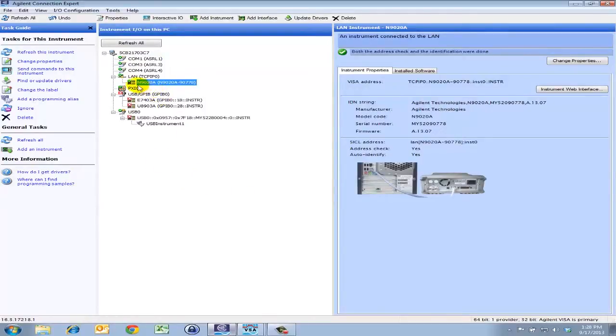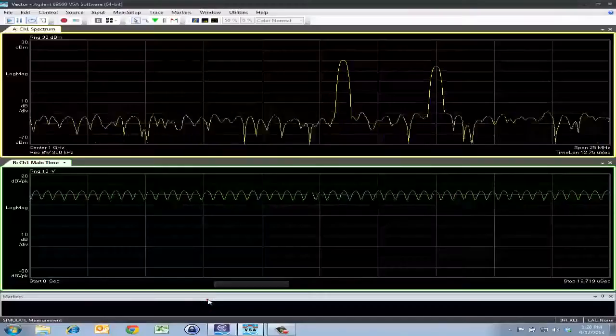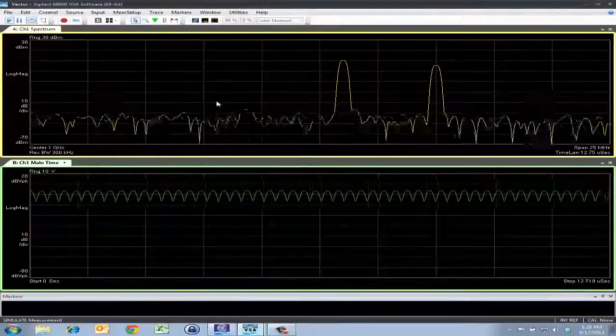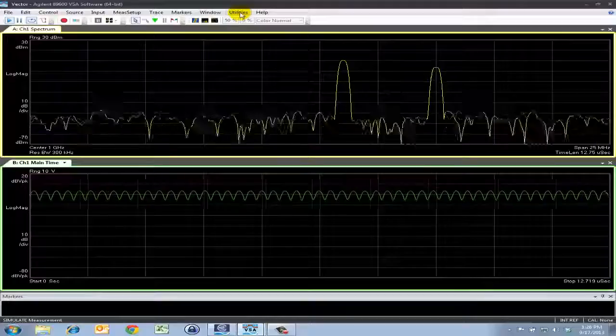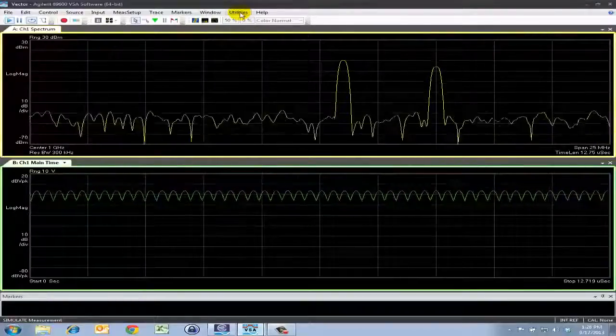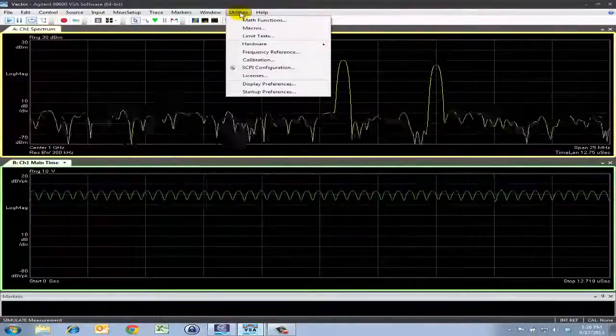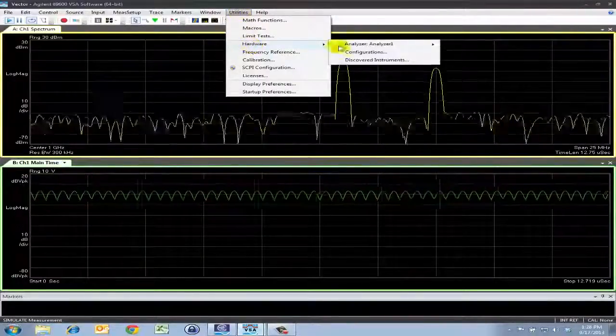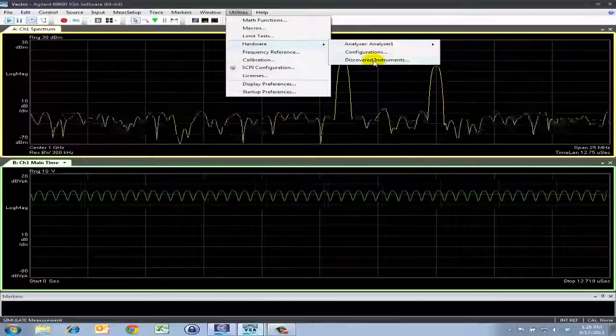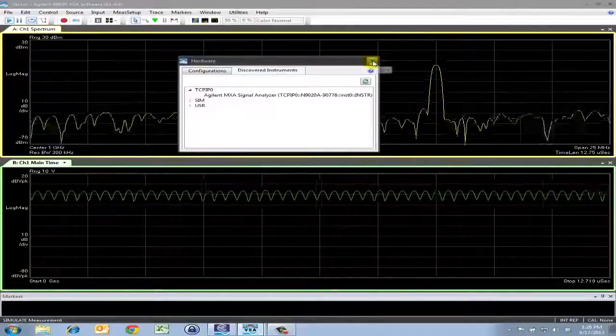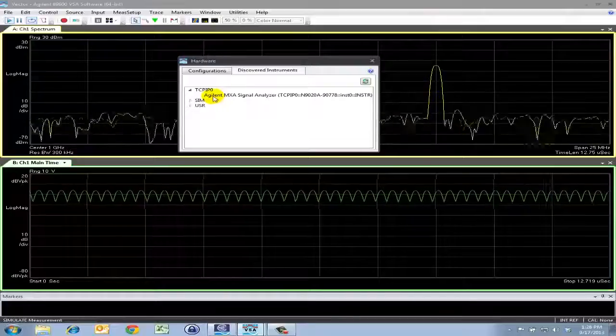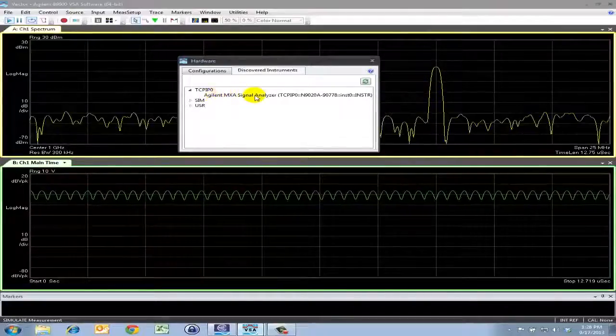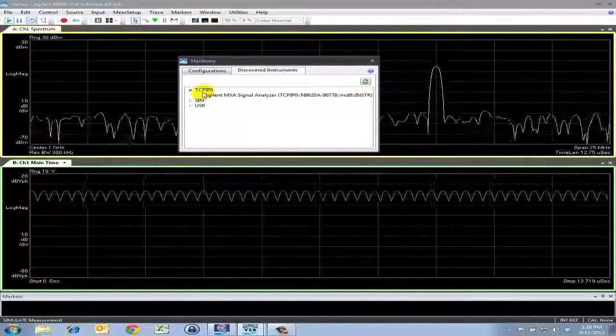So now that we've already established that this connection is good, we can now go back to the VSA software and try to establish a connection. To do that, we'll click Utilities here at the top, then Hardware, then Discovered Instruments. And in this list, you'll see that we have found our Agilent MXA signal analyzer successfully.